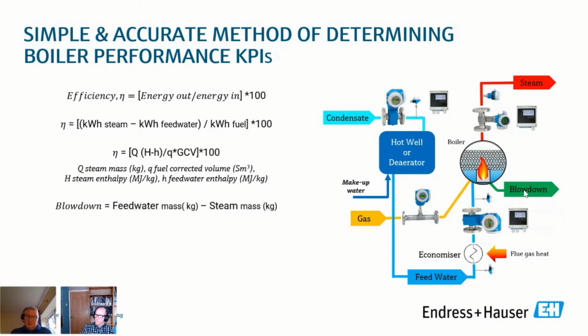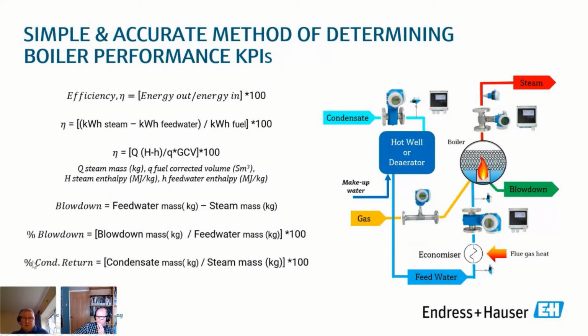It's not unusual to see blowdown values in excess of 10%. And ideally, we should try and get within 10%. This is just wasted energy. So to track this is a good indicator of anything happening. The percent blowdown, obviously, from that is just what the blowdown is divided by that feed water as a percentage. And the condensate return that we talked about is just the condensate mass here divided by the steam mass. So it's the percentage of that steam that we're trying to get back through condensate.